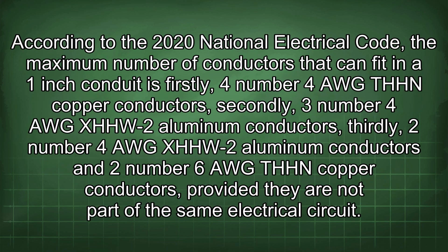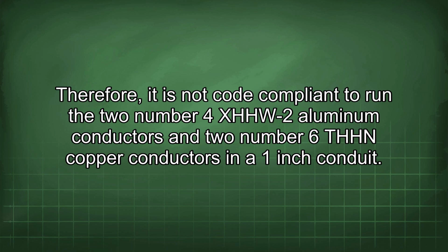According to the 2020 National Electrical Code, the maximum number of conductors that can fit in a 1-inch conduit is, firstly, 4 number 4 AWG THHN copper conductors, secondly, 3 number 4 AWG XHHW-2 aluminum conductors, thirdly, 2 number 4 AWG XHHW-2 aluminum conductors and 2 number 6 AWG THHN copper conductors, provided they are not part of the same electrical circuit. Therefore, it is not code compliant to run the 2 number 4 XHHW-2 aluminum conductors and 2 number 6 THHN copper conductors in a 1-inch conduit.